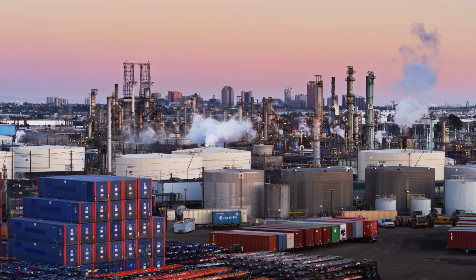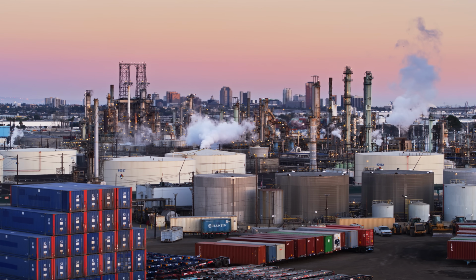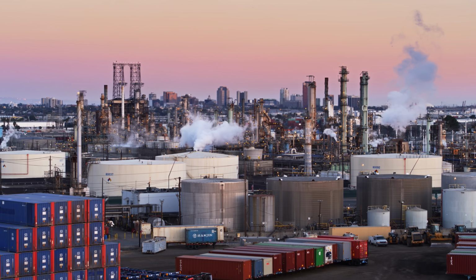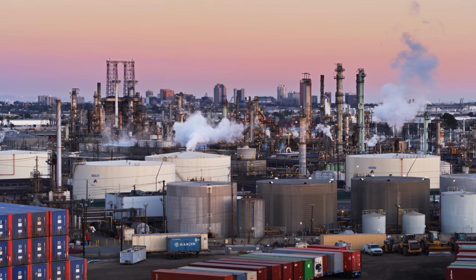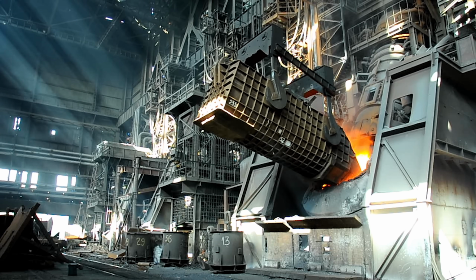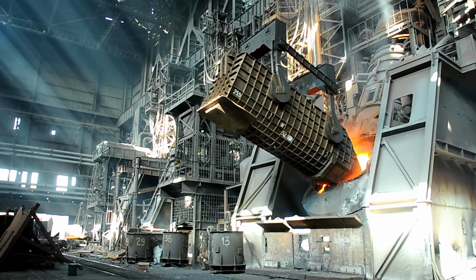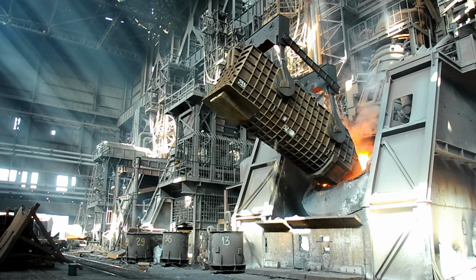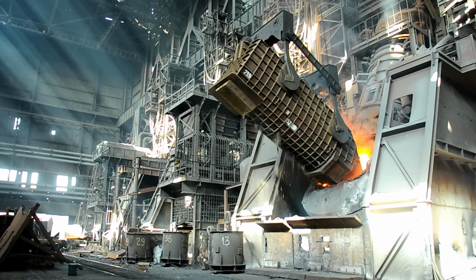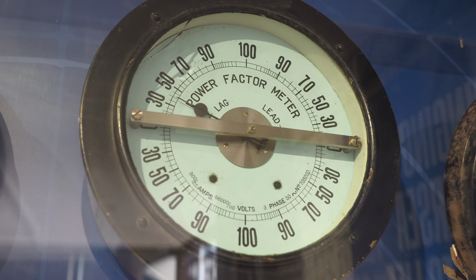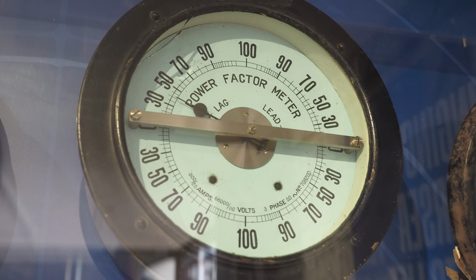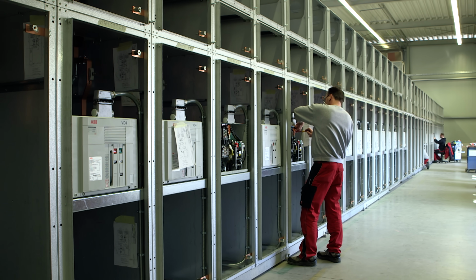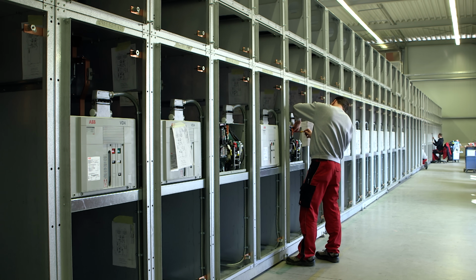Large users of electricity, like factories and refineries, usually have a low power factor because they use a lot of big induction motors. They need comparatively robust and high-capacity connections to the grid, even if they actually consume only a portion of the energy that flows through. So the electric utility installs a meter that can track power factor, or they just come out every once in a while to measure it so they can put it on the bill.